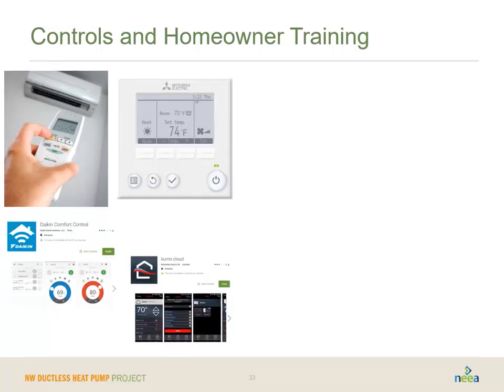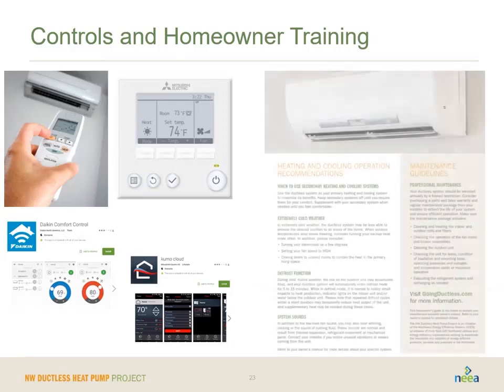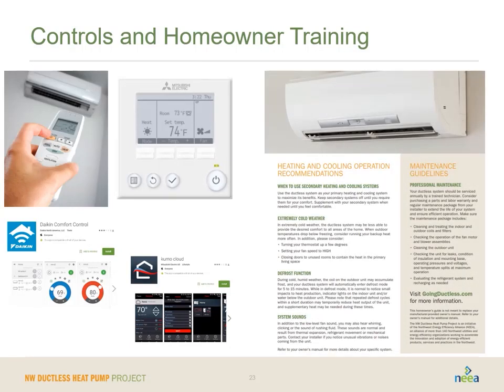Many of these brands also are starting to develop apps that can be used much like a smart thermostat. You can log in, you can check the runtime of your unit, you can adjust the temperature remotely, and it actually will work as a kind of a backup wand or backup controller. So look to that if this is something you think your consumers might be interested in. Talk to the manufacturers and distributors and pick products that actually include these types of apps or smart controllers. And finally, really the number one thing that we find in quality control problems is improper homeowner education and improper homeowner expectations. So you really do want to go through the process of training the homeowner both how to operate their system, what to expect from their system, and the basic maintenance that comes along with these systems.